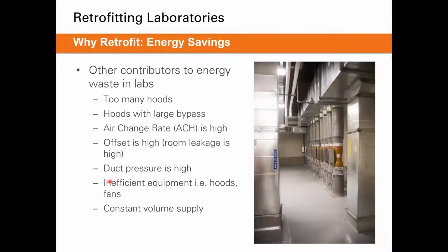And then other contributors would be inefficient equipment such as hoods or fans. And then again, if you were stuck with a constant volume supply, so if you had no way of adjusting the supply once thermal demands are met down to minimum ACH in the room, or if the room is in an unoccupied state, maybe after hours, if you don't have a means of turning down that supply, then that would be constantly exhausting the same amount of air unnecessarily. This list isn't all-inclusive by any means, but these are just a few other things to consider if your goal is energy savings for a retrofit project.